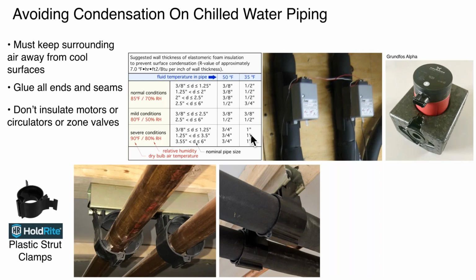When you support piping that is going to be insulated, again, I'll admit we've done systems where we've had stirrup hangers, and what will happen with elastomeric foam quite quickly actually is the foam will sag under the weight of the pipe.